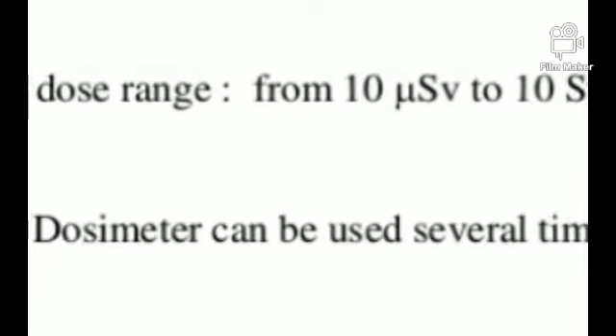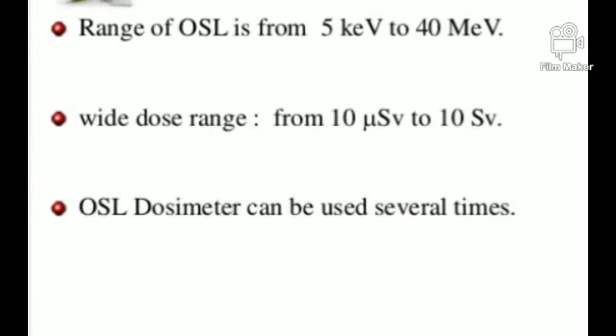For processing, the OSLD device is placed into a reader. Similar to the TLD reader, small rounded disc-shaped chips are inserted into the reader. A laser light is then passed through the chip, which scans it. The key material difference is that OSLD does not use CaSO4 with Dy; instead it uses Al2O3 — aluminium oxide — with activated carbon to record the amount of radiation.